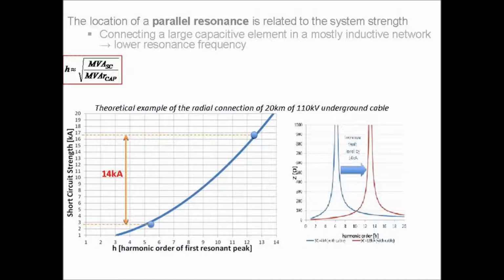And then obviously there's a danger in that, because in order to increase your system strength sufficiently, in some cases in very weak areas, you might need to significantly increase your short circuit currents. So I suppose here's an example where you're in a weak area of the network and you put in a new cable, and it's brought the harmonic resonance down as far as the 6th harmonic. So you can see you've the inductive part, the capacitive part, they've brought it down to the 6th. And you can see the short circuit strength in that area, the kA value, is in or around 4 kA where that resonance occurs. I should say this is for the connection of a 20 kilometre 110 kV cable.